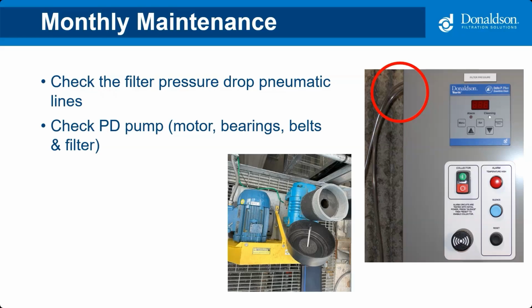Lastly, I talked on the weekly to just do a quick visual check of the PD pump. Monthly, you want to go a bit deeper. Now you want to check the motor and bearings. You're checking for excessive heat, noise, which is usually indicative of bearings going out, or vibration. You're also going to want to inspect the belts, make sure everything's tight, driving the PD pump. And then the PD pump does have a small filter. There's a picture of it there on the screen. You also want to make sure that filter isn't due for replacement.